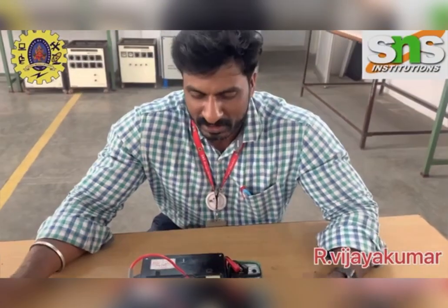Today in class we will discuss the calibration of meters. In the last video we discussed the working principle of the permanent magnet moving coil meter and the moving iron meter for DC and AC purposes. Why do we go for calibration of meters? Every meter we use in the laboratory may be misused by students who don't know how to use it. For example, in a short circuit or a sudden increase in voltage or current, the meter needle may get damaged.